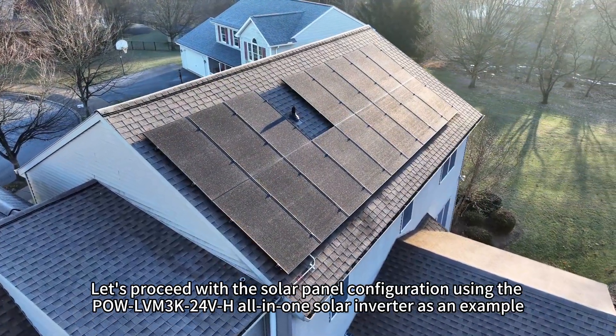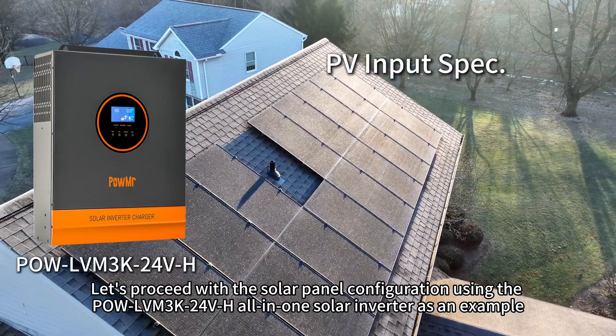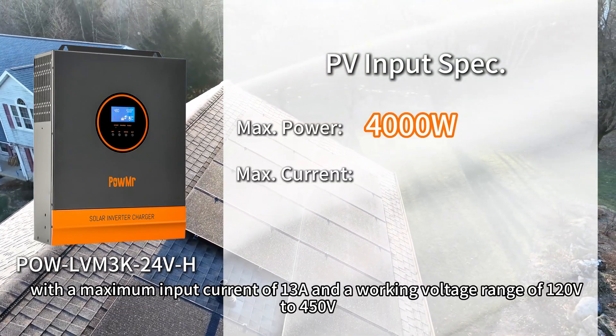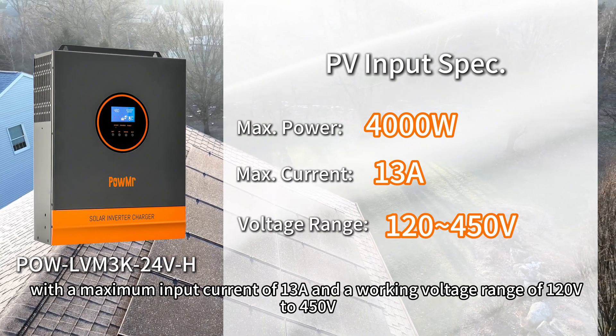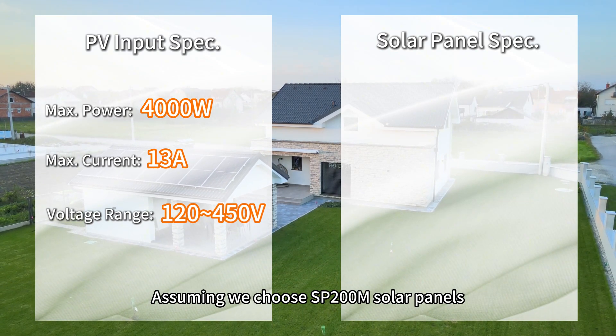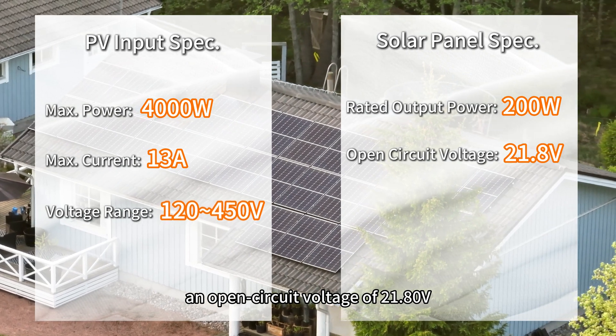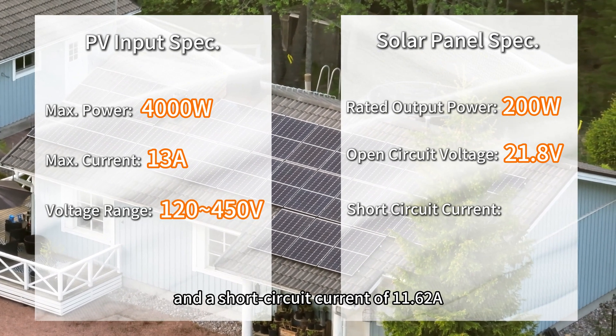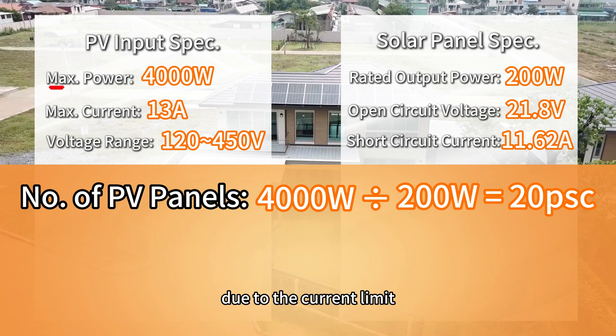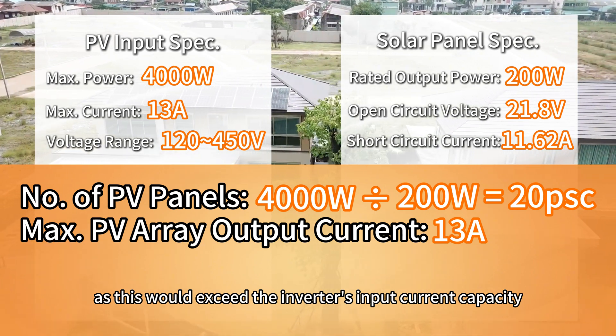Let's proceed with the solar panel configuration using the POW-LVM3K-24V-H all-in-one solar inverter as an example. This system can support a maximum solar array capacity of 4,000W with a maximum input current of 13A and a working voltage range of 120V to 450V. Assuming we choose SP200M solar panels, each with a 200W power rating, open circuit voltage of 21.8V, and short circuit current of 11.62A, we can calculate that up to 20 panels can be connected. However, due to the current limit, parallel connection is not allowed as this would exceed the inverter's input current capacity.